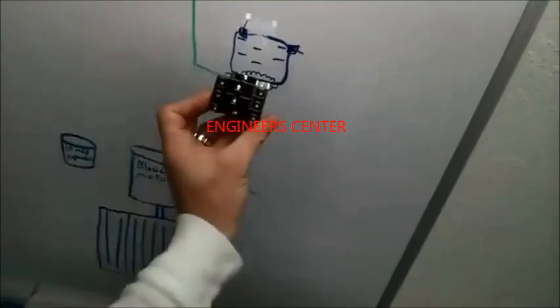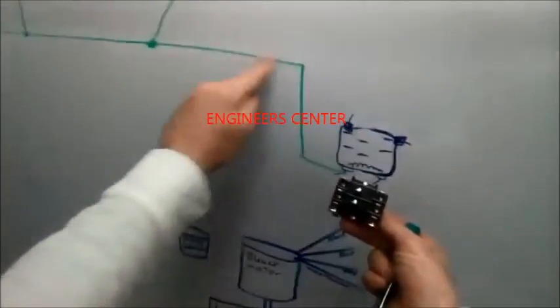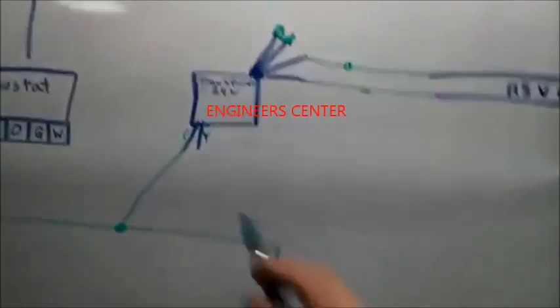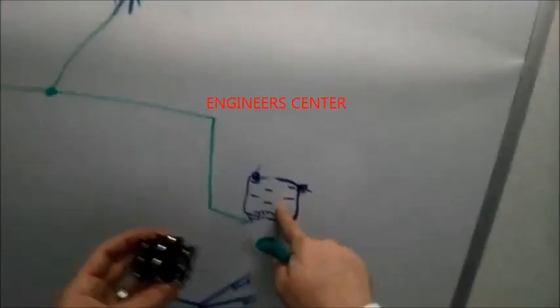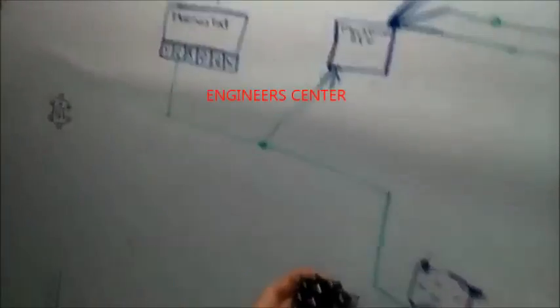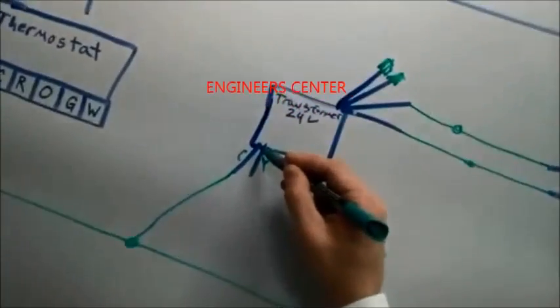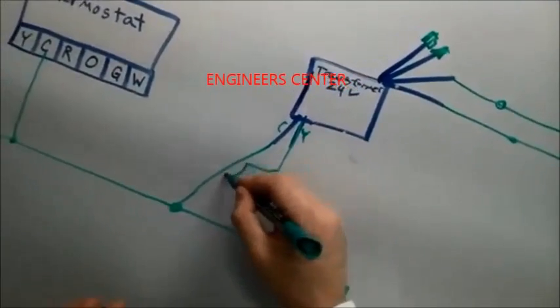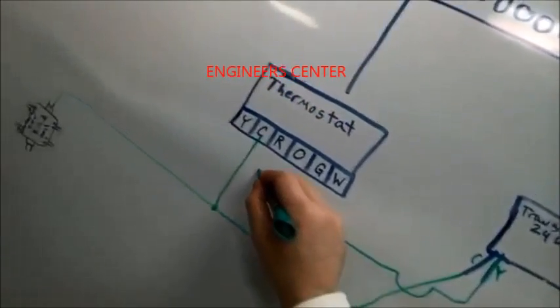Requires 24 volts. We're giving it common through this one. But now, when we want the fan to turn on, we need this thing to close. So what we're going to do is the other side of 24, we're going to bring it over, we're going to jump it, and it goes right to the thermostat.